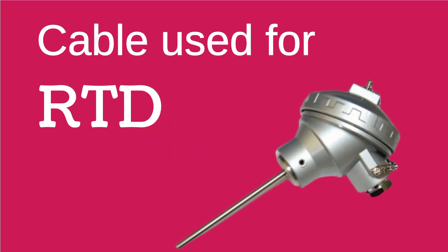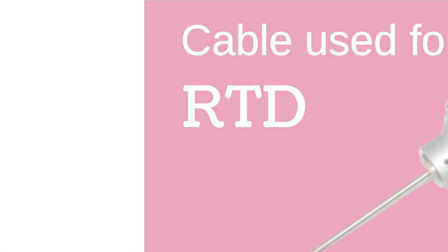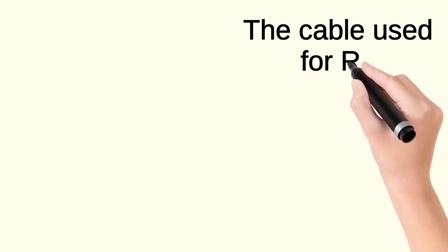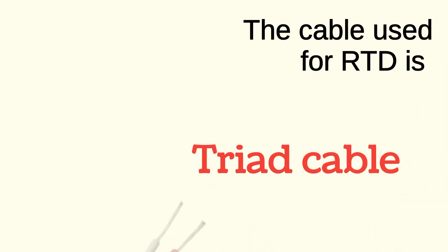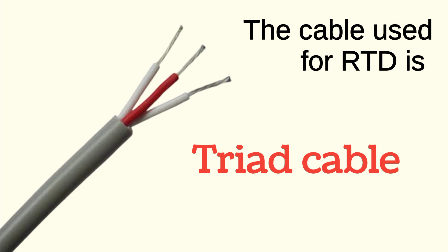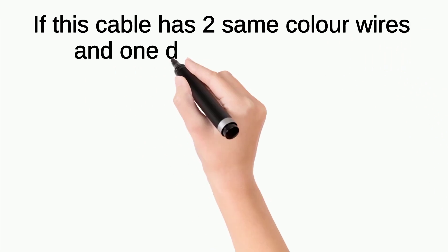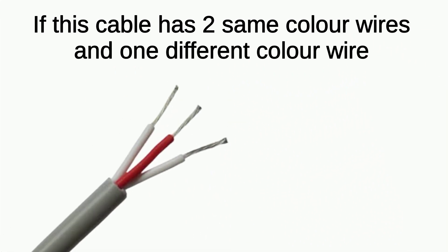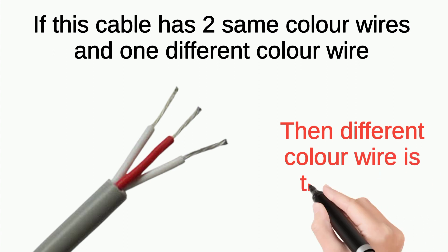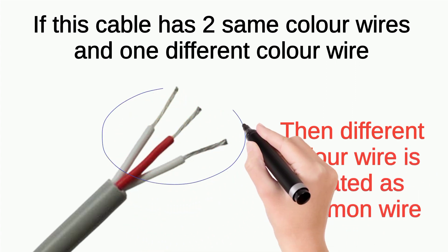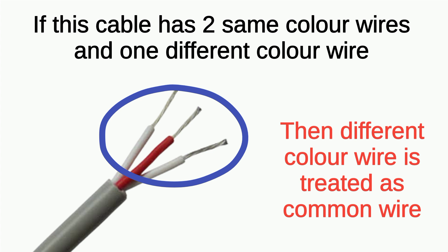First, we will see the cable used for RTD. The cable used for RTD is triad cable, as shown in the image. If the triad cable has two same-color wires and one different-color wire, then the different-color wire is taken as the common wire. For example, the same-color wires are white and the different-color wire is red, so the red wire will be taken as the common wire.